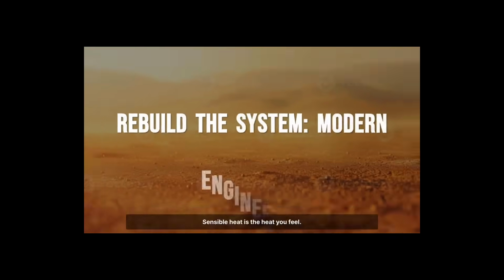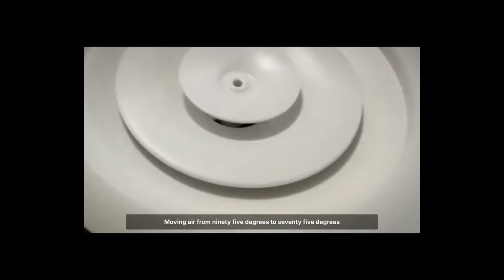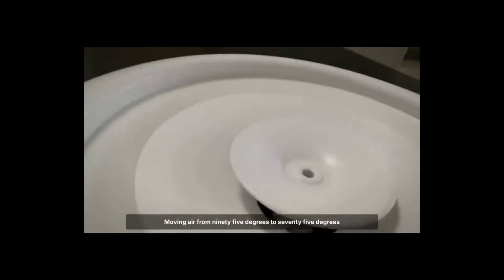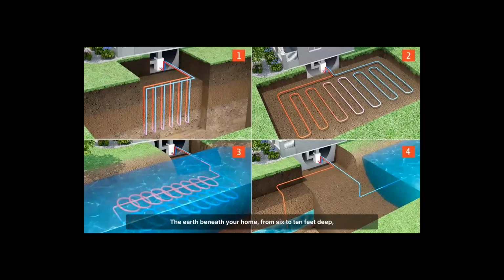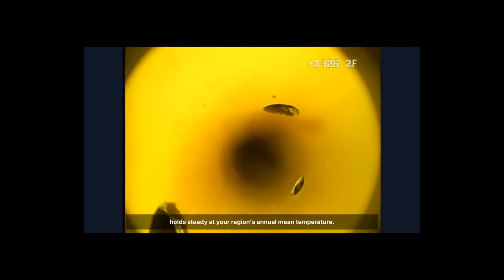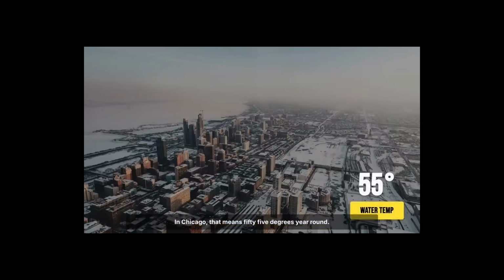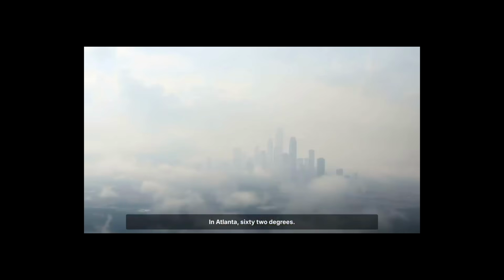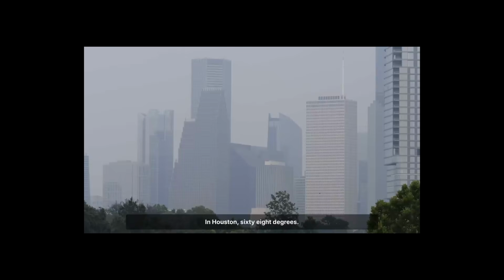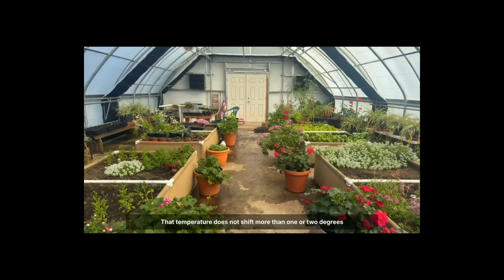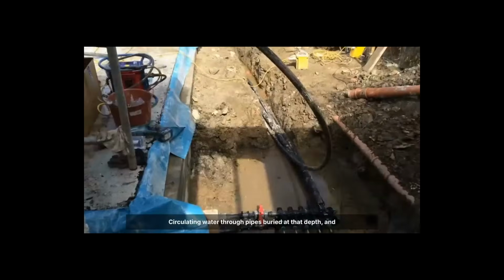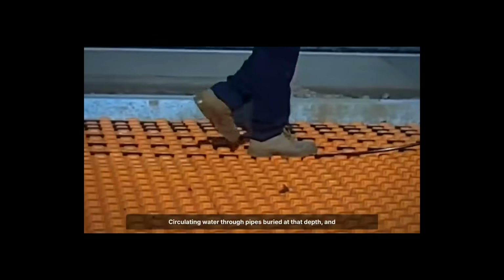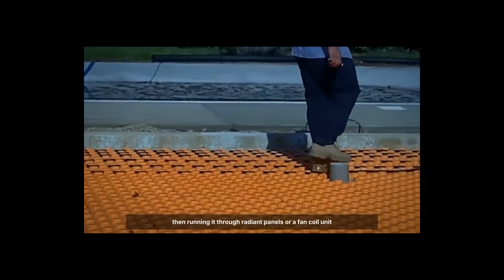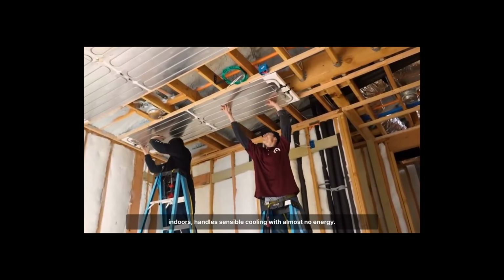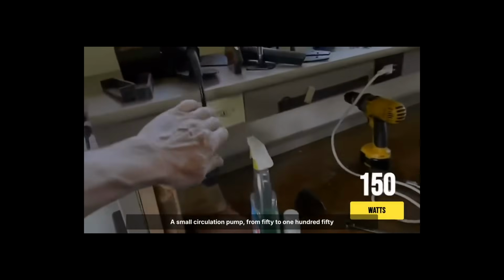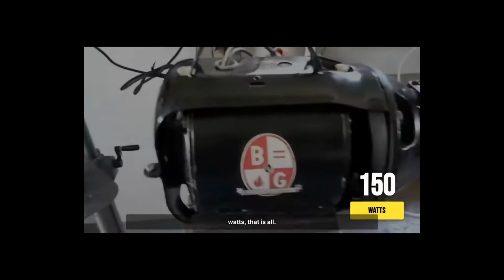Sensible heat is the heat you feel. It is what a thermometer measures. Moving air from 95 degrees to 75 degrees is sensible cooling. The earth beneath your home, from 6 to 10 feet deep, holds steady at your region's annual mean temperature. In Chicago, that means 55 degrees year-round. In Atlanta, 62 degrees. In Houston, 68 degrees. That temperature does not shift more than 1 or 2 degrees across the entire year. Circulating water through pipes buried at that depth and then running it through radiant panels or a fan coil unit indoors handles sensible cooling with almost no energy. A small circulation pump from 50 to 150 watts, that is all.